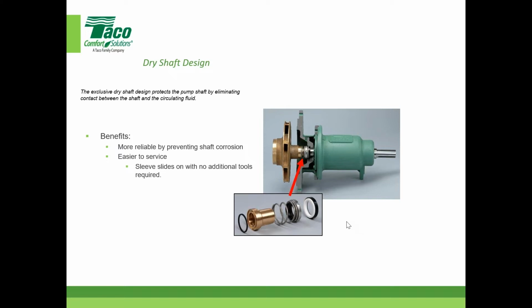I see a lot of people in specifications order a spare seal up front, because sometimes the pump is used as the startup pump, a cleaning or flushing pump, and maybe the seal gets damaged, so you might have to change it right away. That's something to consider, but nonetheless, that's just a cutaway of what you see in the seal there.